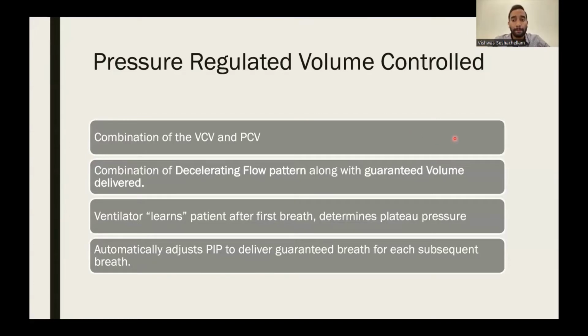Supriya, we have this, right? Yes, sir. By the name of autoflow, this mode is volume control autoflow. And secondly, just to add, even with the Babylogs, if you're using pressure control ventilation, then you get the volume guarantee. So likewise, using pressure control also, you can have a guaranteed tidal volume delivery. Volume guarantee is available in the Babylogs, and with Evitas, you will be getting the autoflow. Wow, that's great.